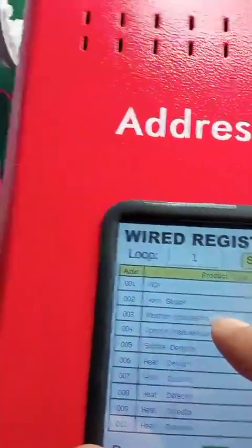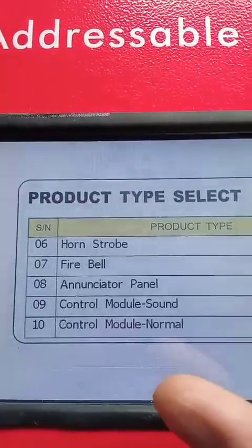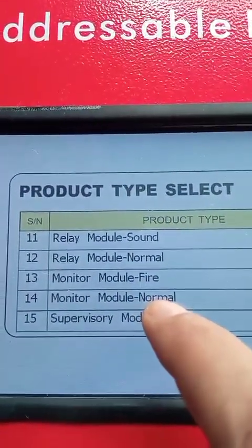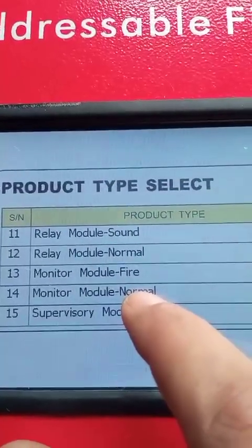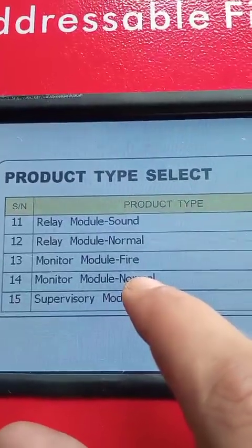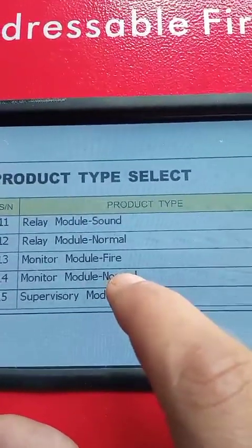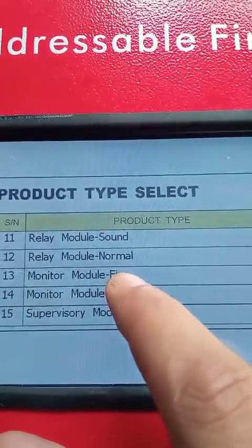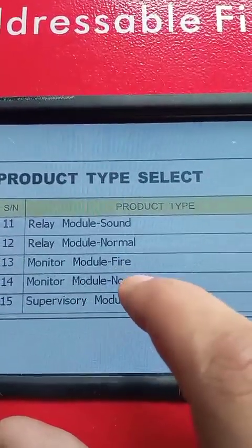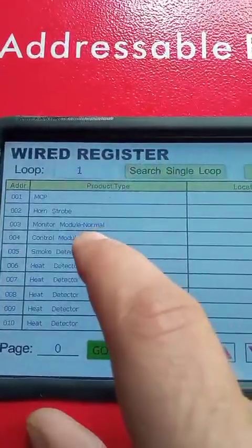For the monitor module I have two options: monitor module fire and monitor module normal. If I choose monitor module normal, then when there is a fire and I press the MCP, it will only activate the buzzer in the panel and not activate the output devices, because it is used only for supervisory. If I choose fire, it will activate the output devices. For now I choose normal to demonstrate.